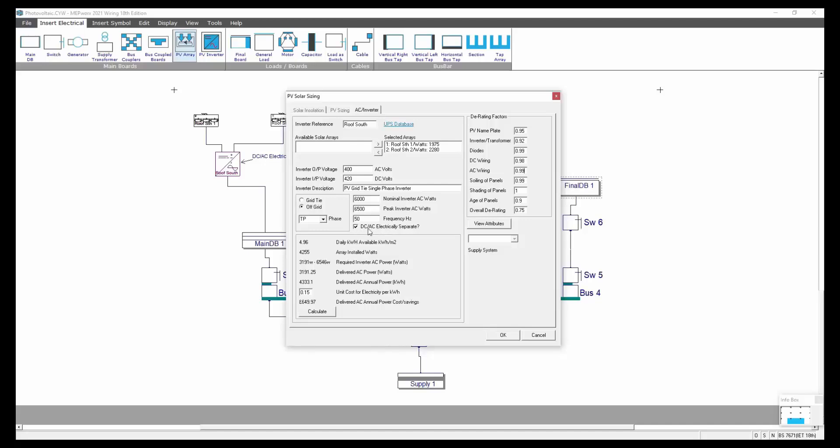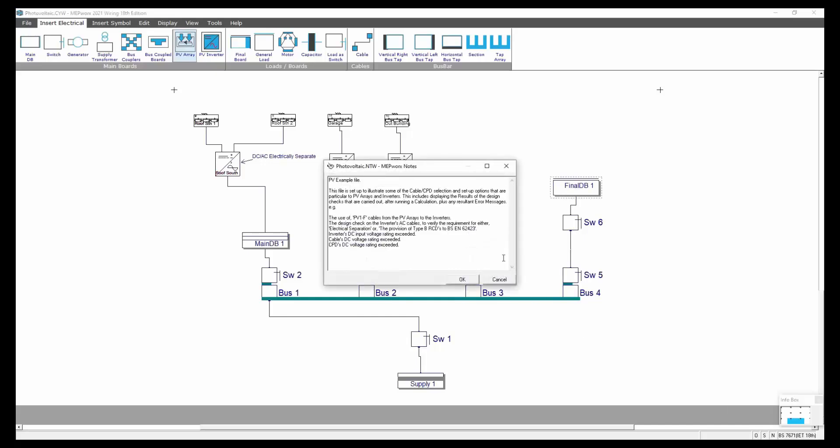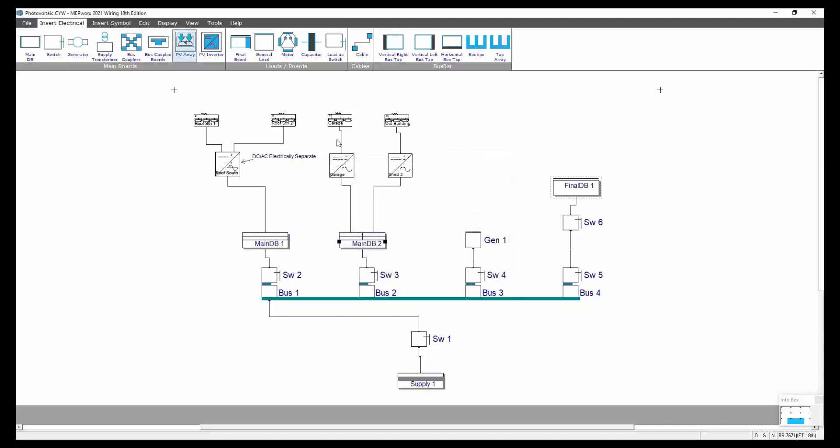Also whether the AC or the DC is electrically separate or not. If they are separate then you don't need a special device. If they're not separate and they're enclosed in the same box then there is a requirement and it does a test to make sure that you've got a BS EN 62423 device protecting that inverter. So all the caveats from the regulation surrounding the panels are built into the calculation.